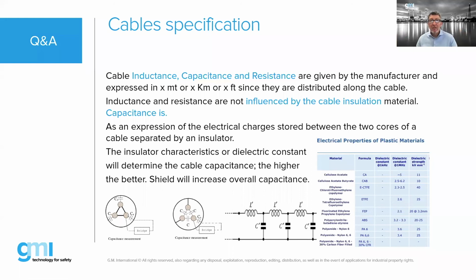Now, inductance and resistance are not influenced by the cable insulation material, while capacitance is. And why is that? Because a capacitor is an expression of the energy stored between two cores. So the insulation between the two cores, or the dielectric constant of that material, makes a difference on the capacity of the cable. The better the dielectric constant is, the less capacitance you have, and the less capacitance, the better the cable, because you can go longer distances.